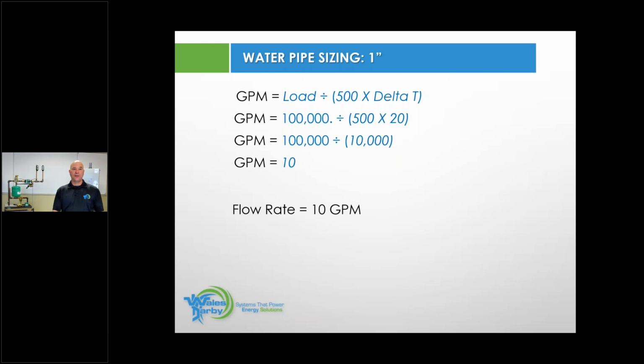So here we have a 20-degree delta T. With that 20-degree delta T, we're always going to do the math in the parentheses first. 20 times 500 equals 10,000. 10,000 divided into my 100,000 BTU boiler gives me my flow rate of 10 GPM. That's the example we went over here live.